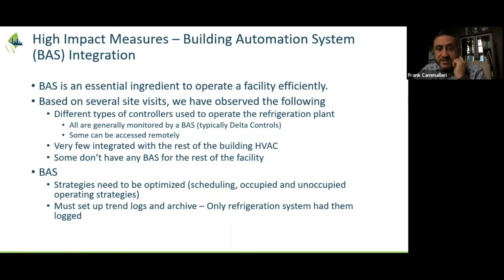On the building automation system front, some key things we look at are whether they can be optimized—things like scheduling, occupancy, and unoccupied operating strategies. Also optimizing equipment operation for the rest of the facility, making sure economizer mode is used properly, and taking advantage of any heat that could be used from the refrigeration system within the facility.